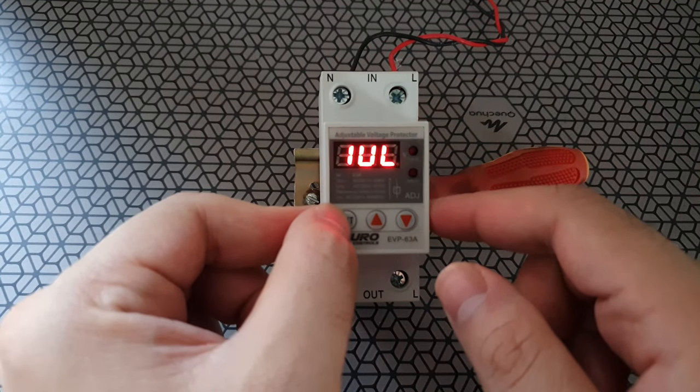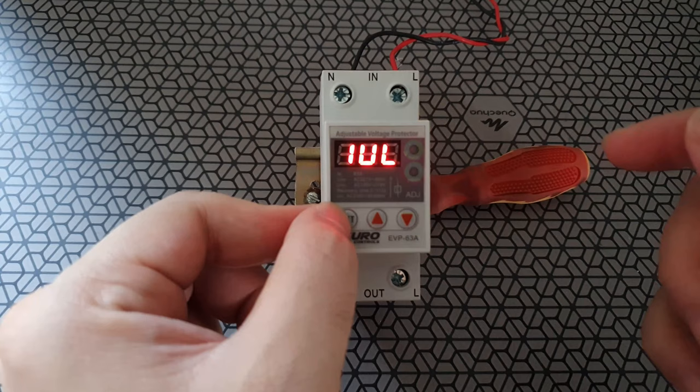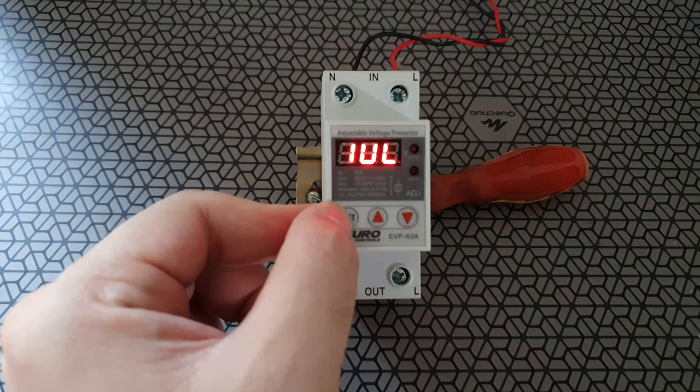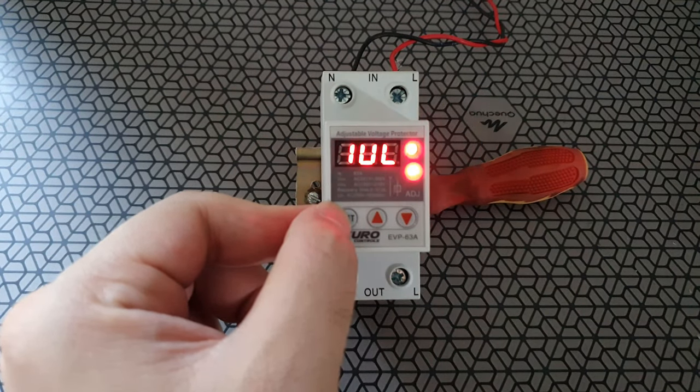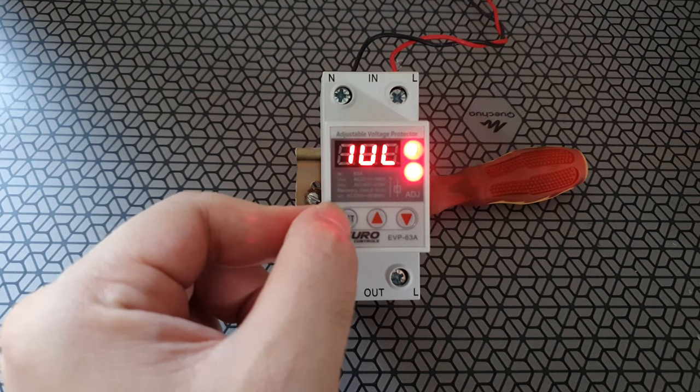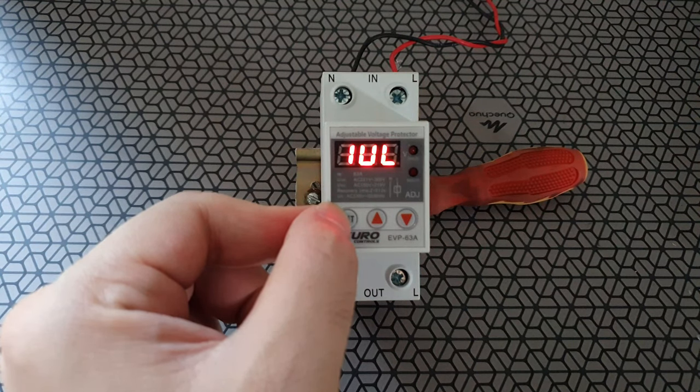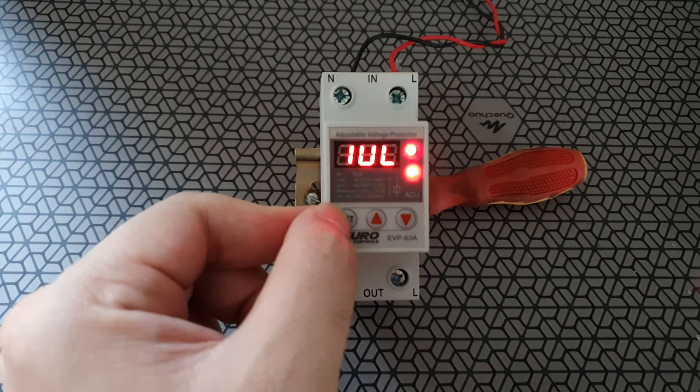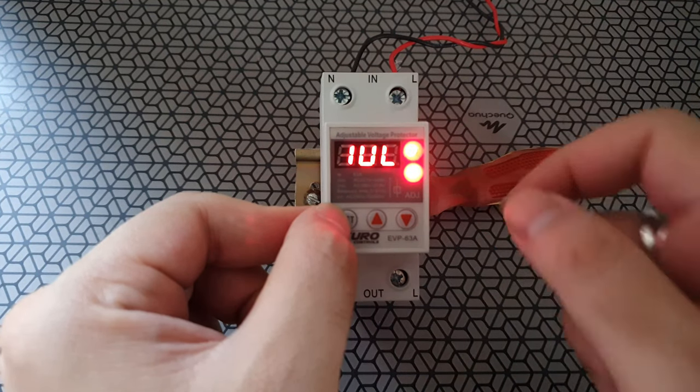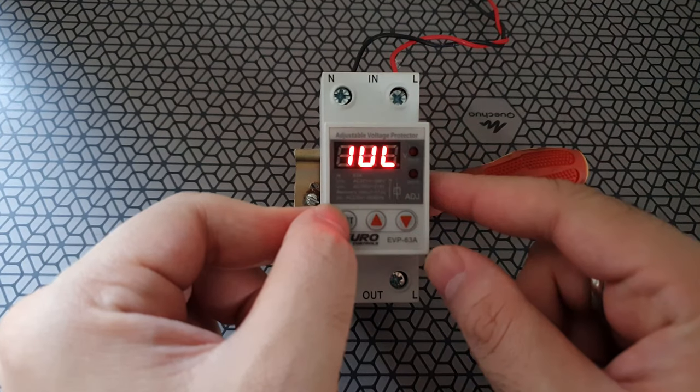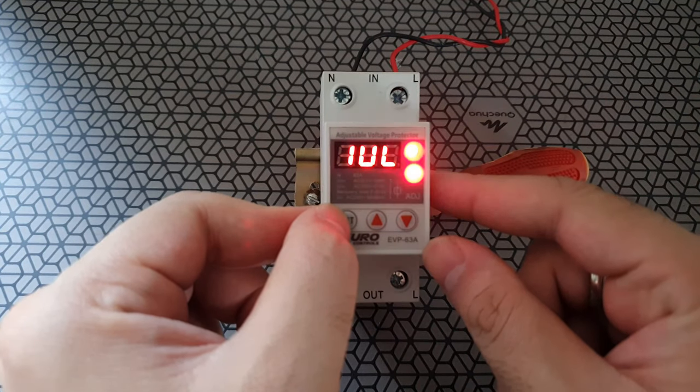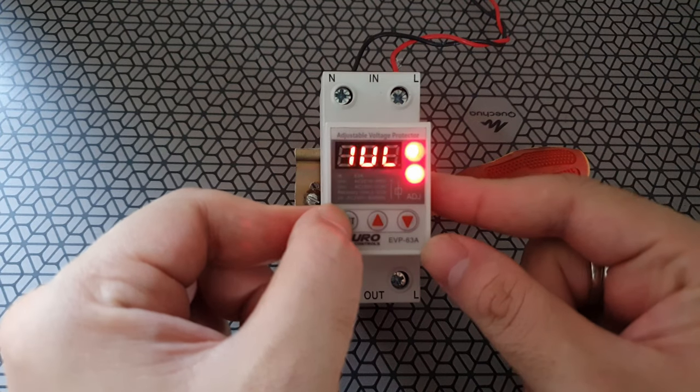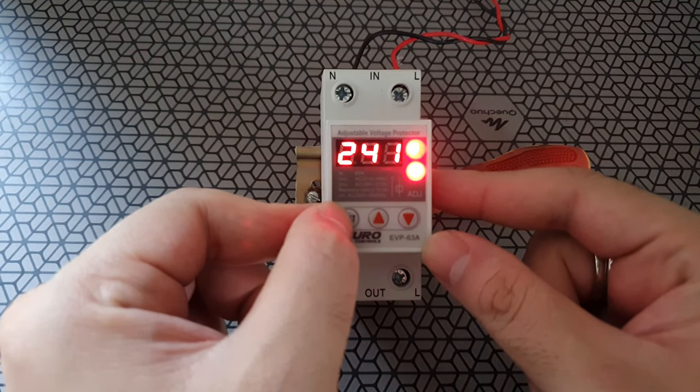Another incredible thing that this device does in the last menu, is tell you the last five instances of high voltage or low voltage cutoff. So it's got a display here, which right now shows 1UL. Which means the last time there was an under voltage cutoff. And this will change to UH in case there was a high voltage cutoff. It's a very intelligent device, it can show you a log of the last five cutoffs.